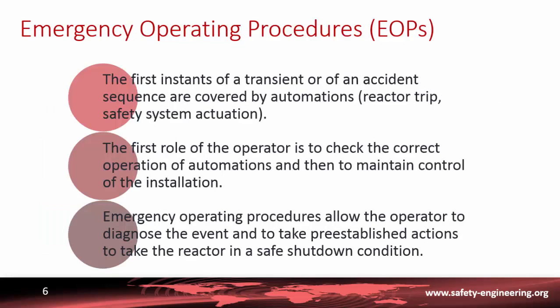The third important element of the operating rules is the Emergency Operating Procedures, or EOPs. The initial response to a transient or accident sequence is covered by automatic actions — reactor scram or reactor trip and safety system actuation. The first role of the operator is to check the correct operation of these automatisms and maintain control of the installation. The EOPs allow the operator to diagnose the event and take pre-established actions to bring the reactor to a safe shutdown condition.